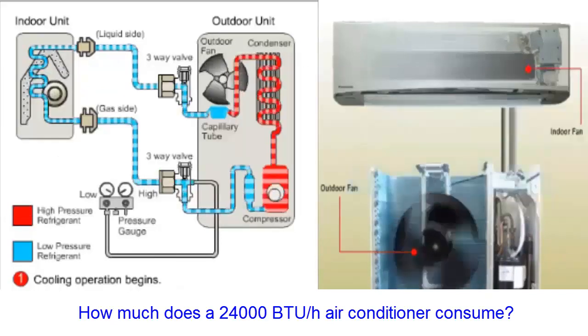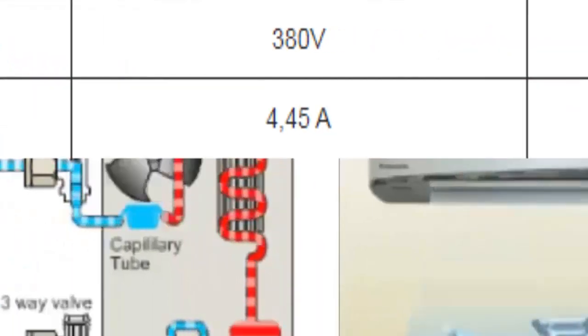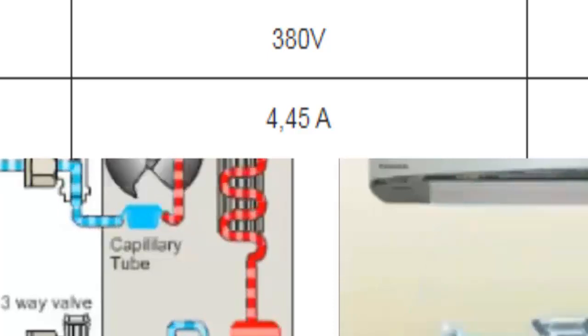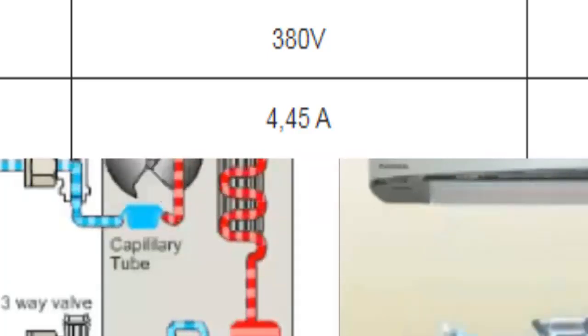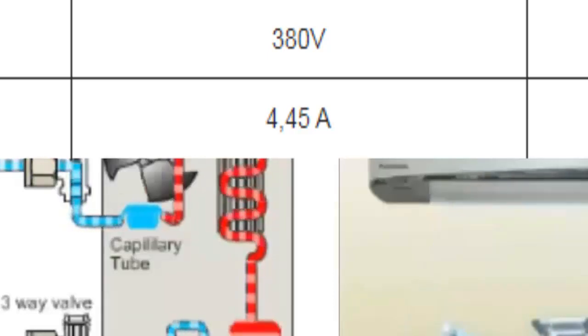For a three phase power supply voltage of 380 volts, the average current consumption of the equipment at 100% capacity is 4.45 amperes. For a three phase power supply voltage of 400 volts, the average current consumption at 100% capacity is 4.24 amperes.